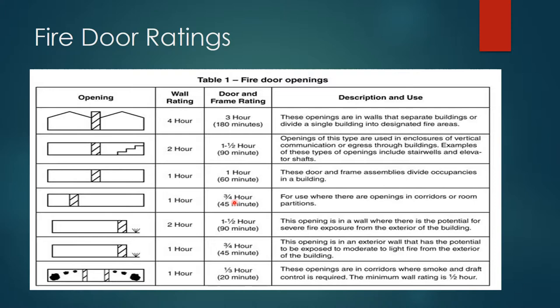A 1-hour, 60-minute door is defined to separate occupancies in a building, though in healthcare I've typically seen more 2-hour than 1-hour. When you get down to the 1-hour and 3/4-hour door, this is really getting into partitions, corridors, smoke barriers, hazardous spaces, and non-sprinklered egress corridors. A 1-hour fire-rated corridor or room will have a 45-minute door.